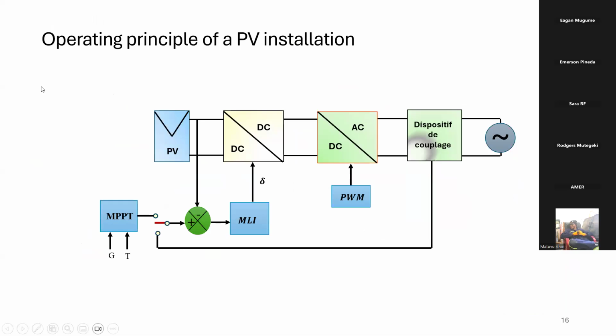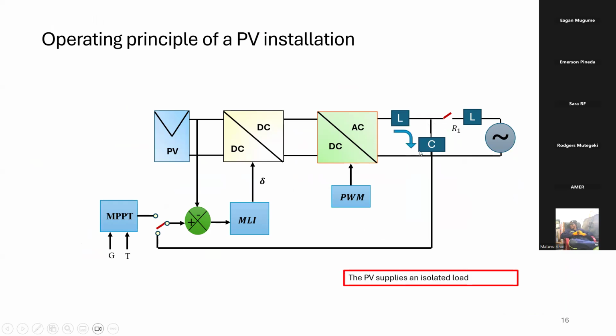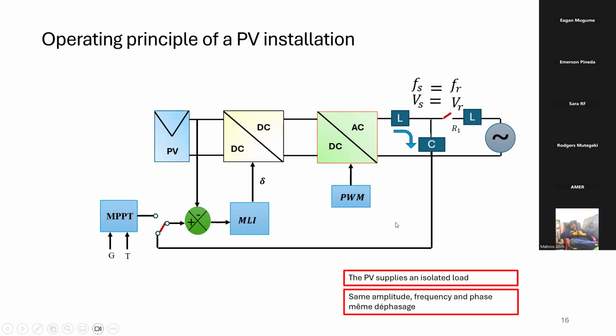Every PV installation must be equipped with these components: the PV, the DC-DC converter to extract the MPPT from the PV, and the DC-AC inverter. The principle consists of injecting the load after the connection between the inverter and the grid, when there is the same frequency, the same voltage, and the same concordance of phases. We can inject active power, and we can inject or absorb reactive power according to grid needs.